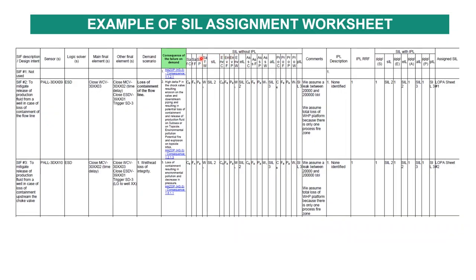The SIL assessment worksheet shows the sensor, logic solver, and final elements. The demand scenario comes from HAZOP. You put the risk graph here, input the consequences — whether disaster or catastrophic — exposure, whether avoidance is possible, the demand rate, and you arrive at a SIL. The same process applies for environment and production. You then look at independent layers of protection (IPL). Based on the protection layers available, you reduce the SIL level. Finally, you arrive at a certain SIL, and if it is SIL 3, you proceed to LOPA.